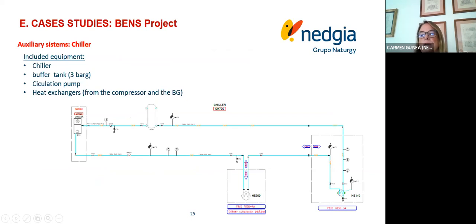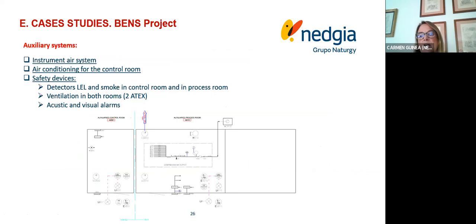Among the auxiliary equipment installed in the plant, we have a chiller to cool the biogas and a buffer tank for water, a recirculation pump, and the heat exchangers, one for the biogas and another one for the compressor. Besides, other auxiliary and safety systems are installed in this plant, such as the instrument system, the air conditioning, and the safety devices, such as gas and smoke detectors. We have methane and smoke detectors in the control room and in the process room. Besides, the ventilation in both rooms is by ATEX blowers. And we also have acoustic and visual alarms to protect the system.